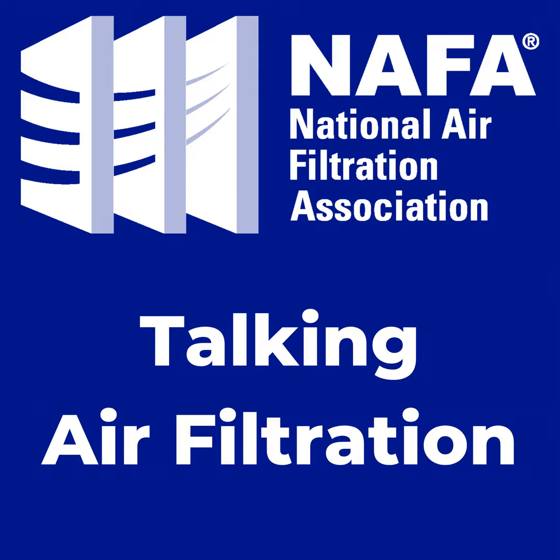That's the case with any electrostatic charged media. If you're going with a MERV 13 filter that has a low pressure drop, you're going to eventually lose that efficiency and not have that performance. So if you're looking for a MERV 13 that will stay a MERV 13 forever, we have to look at different options. Nanofibers are going to be a way we can hopefully bridge that gap between the performance we want from these MERV 13 electrostatic charge filters, but aren't currently getting. And then ISO 16890 uses an IPA vapor discharge. So it might be another thing that was discussed and has been brought up in previous NAFA meetings.